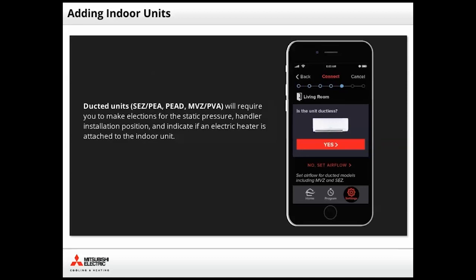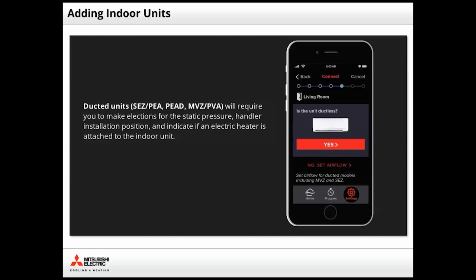Kumo Cloud will read the capabilities of the indoor unit and may display this screen. If the unit is ducted, you will need to tap No Set Airflow to make adjustments and additional unit settings such as static pressure and installation position. However, for the purposes of this tutorial, we'll go ahead and tap Yes.